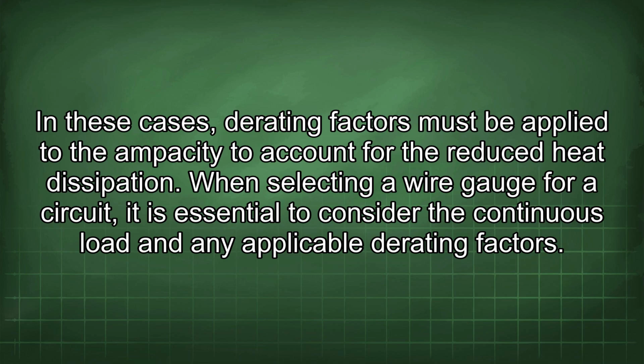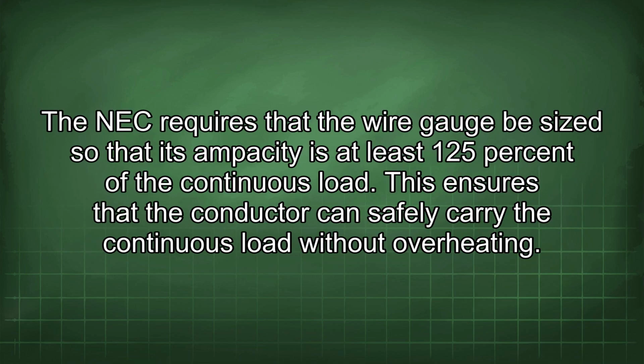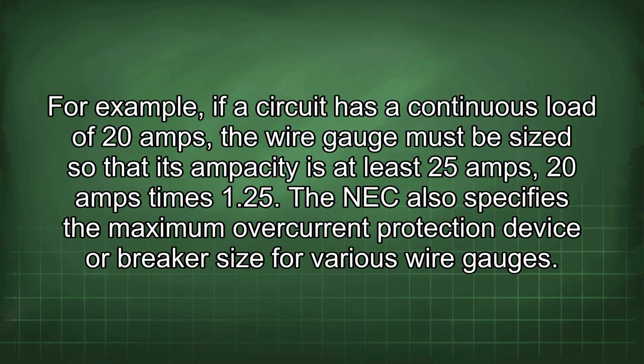When selecting a wire gauge for a circuit, it is essential to consider the continuous load and any applicable derating factors. The NEC requires that the wire gauge be sized so that its ampacity is at least 125% of the continuous load. This ensures that the conductor can safely carry the continuous load without overheating. For example, if a circuit has a continuous load of 20 amps, the wire gauge must be sized so that its ampacity is at least 25 amps, 20 amps times 1.25.